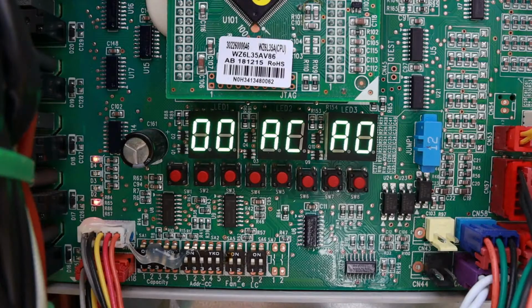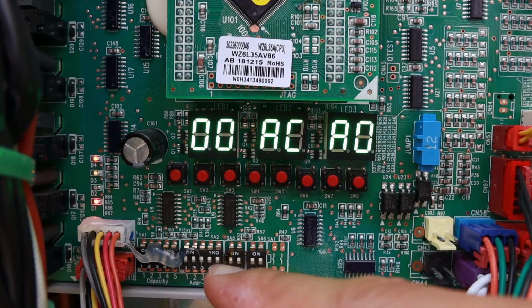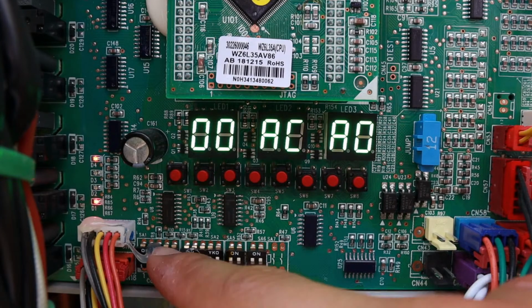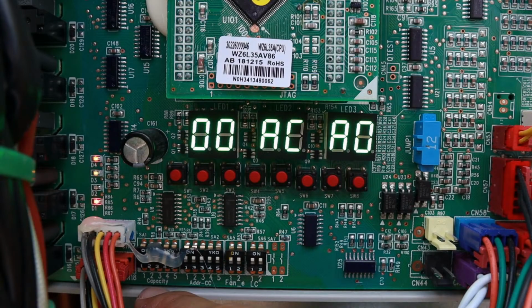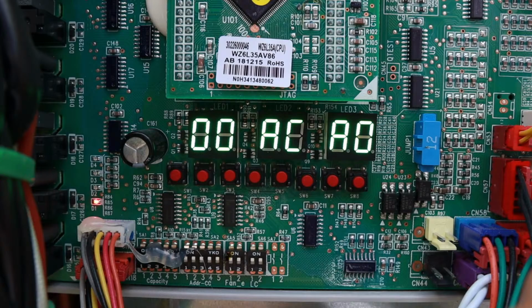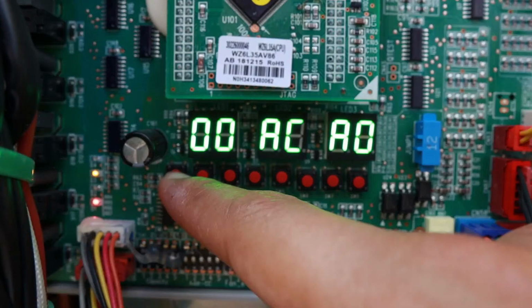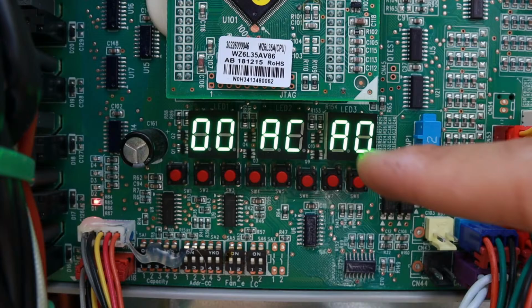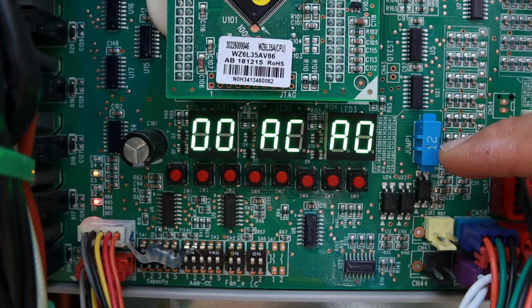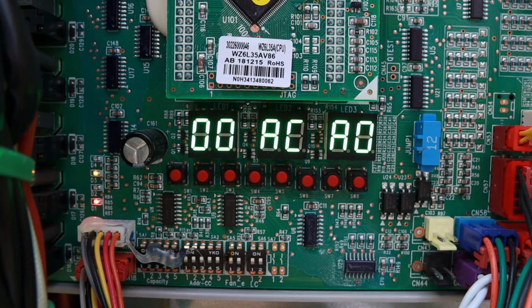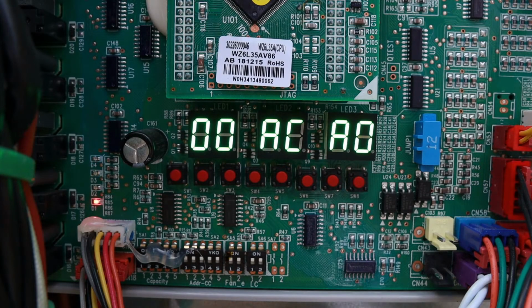Walking you through the board, you can see that right here at the bottom of the board we have the dip switches. Then we also have SA1, which is a dip switch for capacity. This one has silicone glue on it. Do not touch it, do not remove it, leave it alone so we can get ready to work on the unit. SW1 through SW4 are the buttons on the main board. We have LED1, LED2, and LED3 that are showing us the display, and a jumper cap right next to it. Make sure that this jumper is installed on the board. If it's a brand new unit, you won't be able to miss it, but in case you're working on a new board or a replacement board, then make sure that the jumper is there. It could be that the previous technician removed it, didn't know what to do with it, so make sure that the jumper is there.